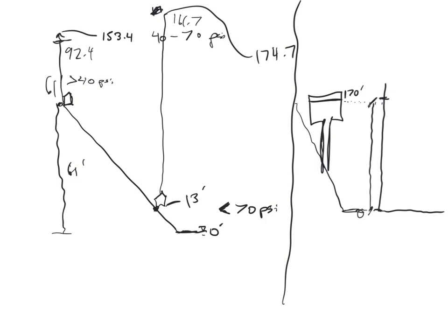As far as what kind of flow your pump has to provide, remember you're going to be locating a point on this pump curve just with one point. It's going to be a Q and an H, and you have to pick those two. What value you put in there for the H is going to affect directly the shutoff head. Remember that what EPANET picks for this intersection point is equal to 1.33 times, we'll call this H star and Q star, H star.